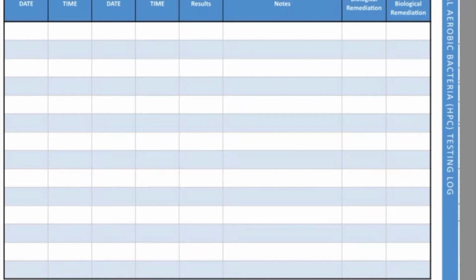In addition to all the other inspections and tests you do when you record, you're also required to perform a weekly microbiological test. That test goes by a lot of names. Sometimes it's called HPC, which stands for heterotrophic plate count. Sometimes it's called total aerobic bacteria, which I think is a better name for it. And sometimes you might just call it the dip slide, since it's kind of like that. So we want to record the results of that test and how and where we took that sample.